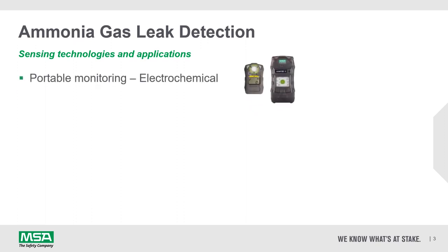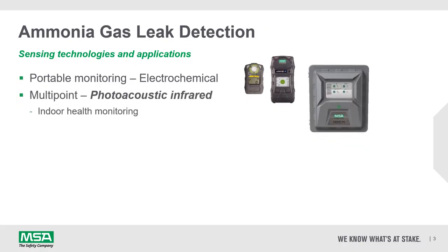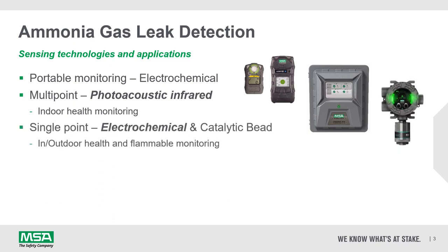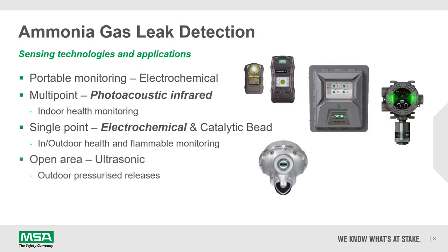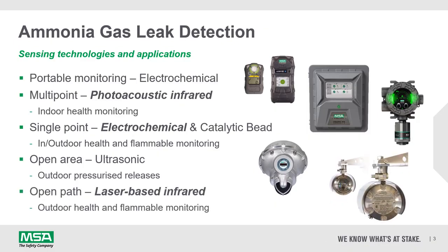A range of sensing technologies and product configurations exist for the detection of ammonia. These include portable monitors using electrochemical cells, multi-point detection systems which use sampling systems in combination with a photoacoustic infrared technique, single-point gas detectors using electrochemical cell or catalytic bead technology, open area detection using ultrasonic techniques, and finally open path detectors using a laser-based infrared technology. For the purpose of this presentation, we're going to touch on photoacoustic, electrochemical cell, and in particular laser-based technology.